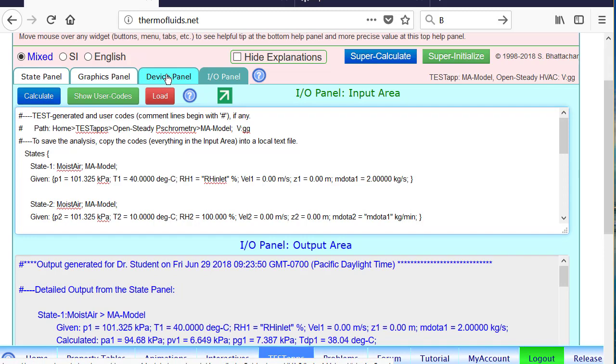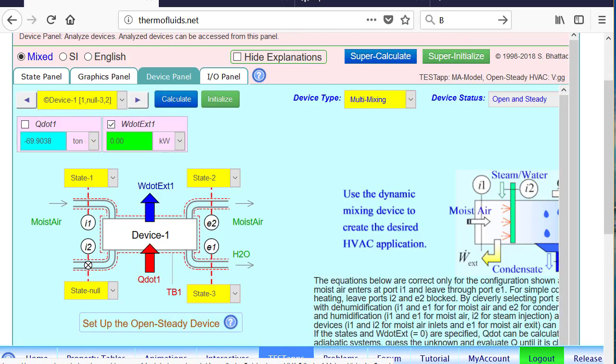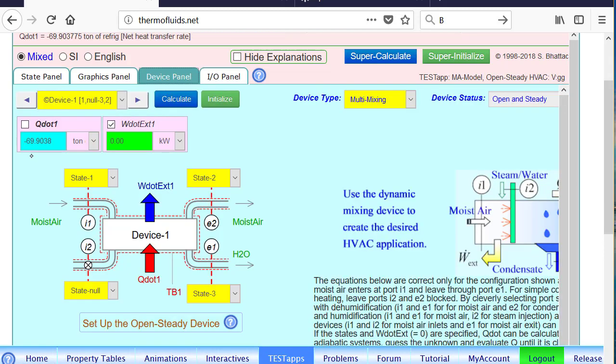All the states are updated. Notice that from 33 ton, the refrigeration capacity has more than doubled. So that means that we need to remove a whole lot more heat because of high humidity at the inlet. That's why air conditioning becomes very expensive in humid weather compared to drier weather. You can do further parametric study to explore that reducing the temperature doesn't cost much refrigeration capacity compared to reducing the relative humidity.